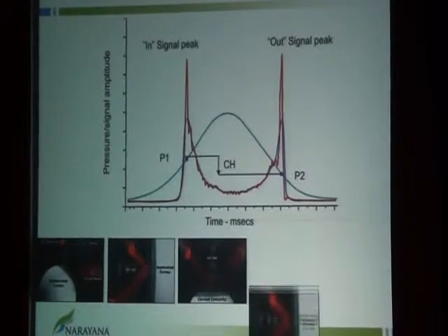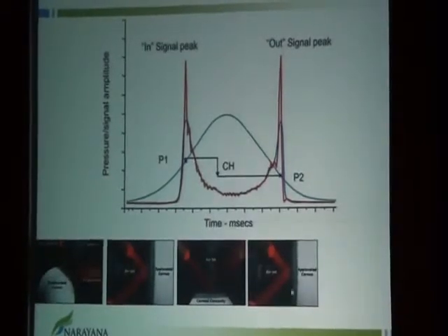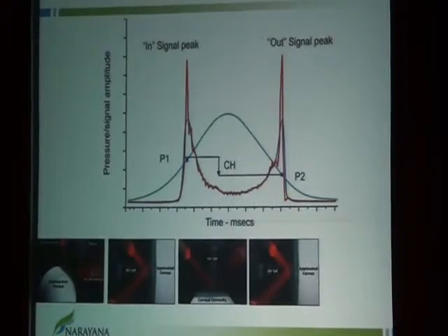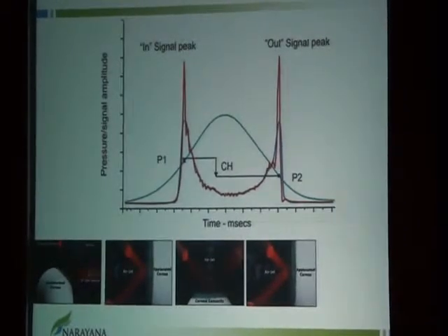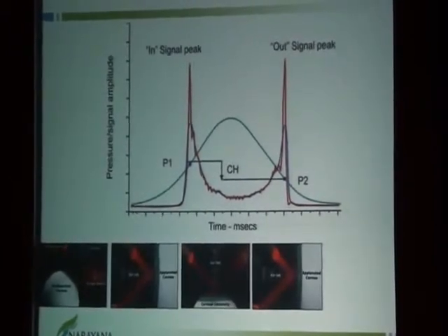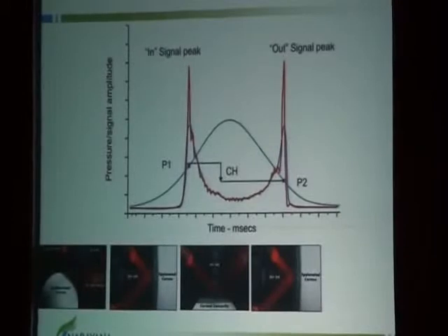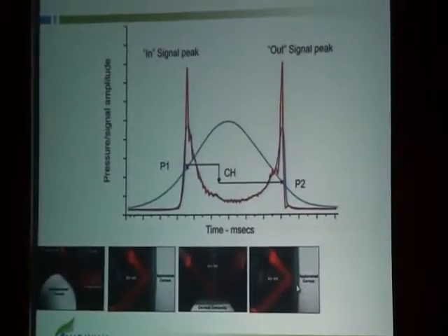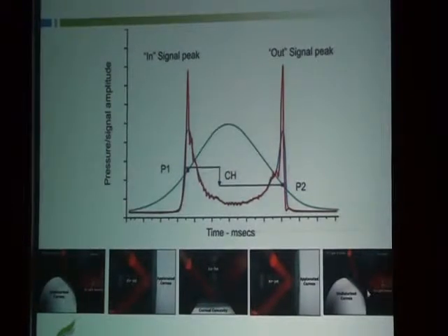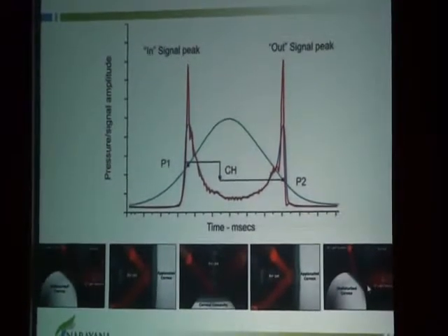Once the air pulse is stopped, the cornea starts returning to its normal convexity. During this process, it passes through applanation once again. So there is a second applanation event, and this is again recorded, and it then finally reaches its undisturbed convex state.